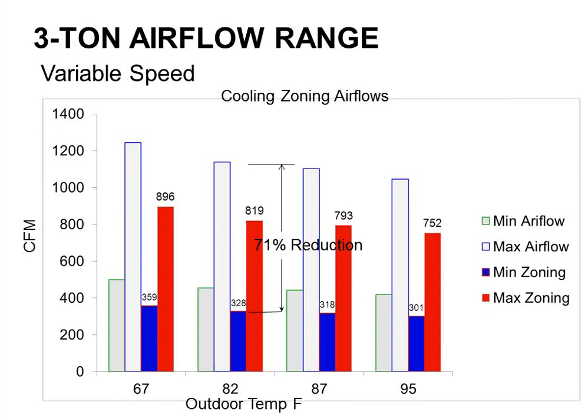As the zone damper starts throttling back, we sense that increased static pressure, and we modulate the indoor fan accordingly. And as the indoor air fan modulates down for less airflow, we're also inadvertently putting in caps on the maximum compressor speeds and condenser fan speeds. So it all kind of works in sync with one another.